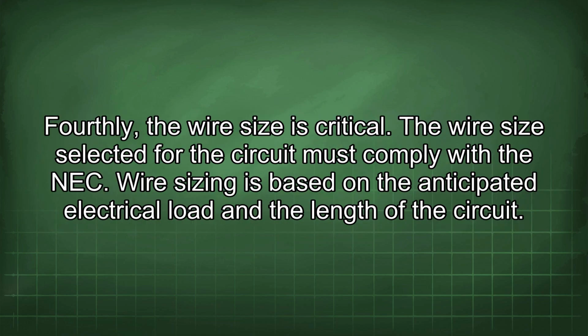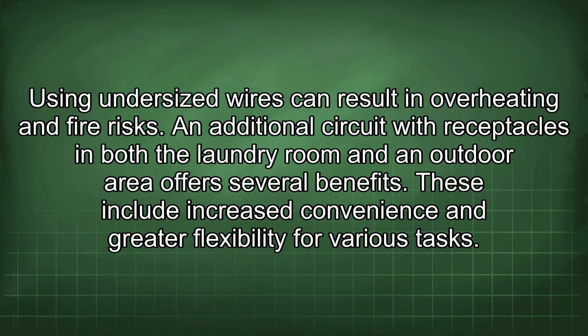Fourthly, the wire size is critical. The wire size selected for the circuit must comply with the NEC. Wire sizing is based on the anticipated electrical load and the length of the circuit. Using undersized wires can result in overheating and fire risks.